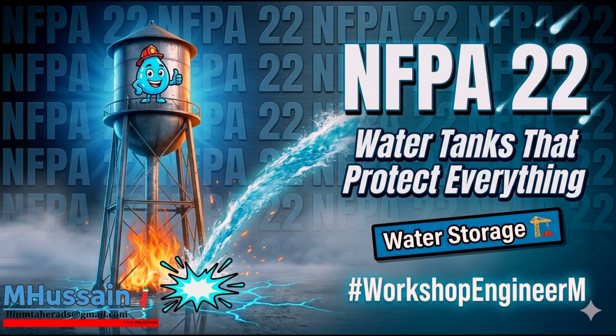It has to be bolted to the combination inlet-outlet fitting. You essentially hover a massive coaster over the drain. That's a great visual. And if you examine the specific diagrams in Annex B, specifically Figure B1P, the dimensions are rigid. What are we talking about here? A standard vortex plate is typically a 48-inch by 48-inch square of heavy steel, and it must be placed not less than 6 inches above the bottom of the tank.